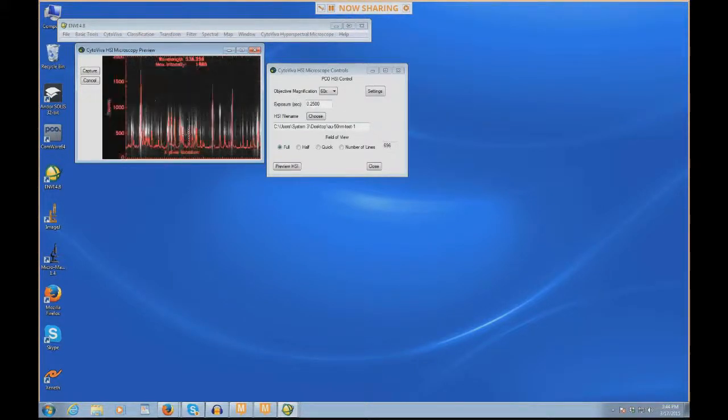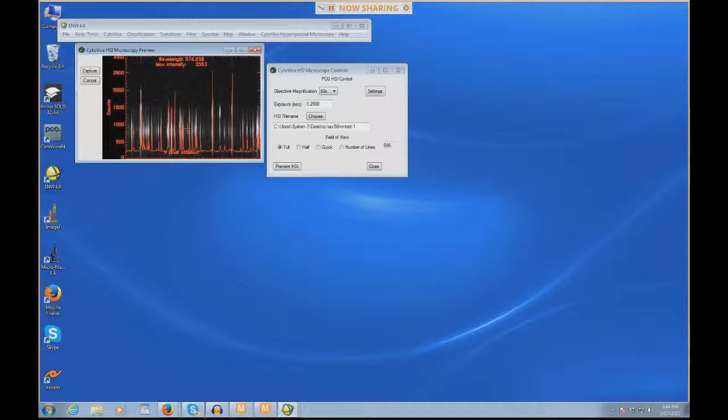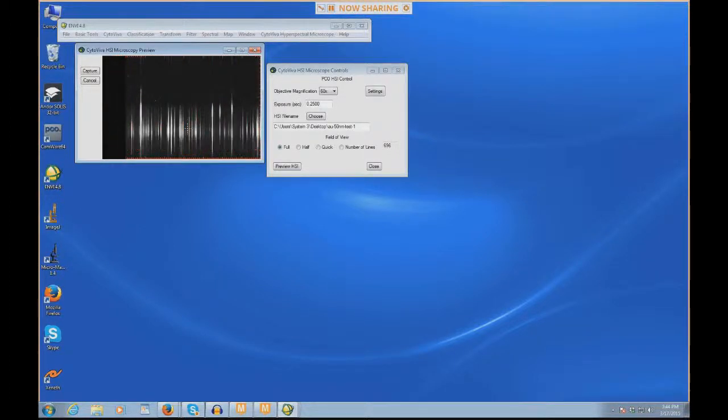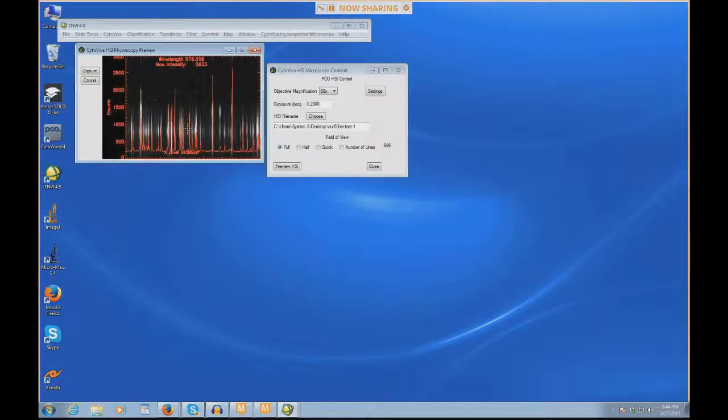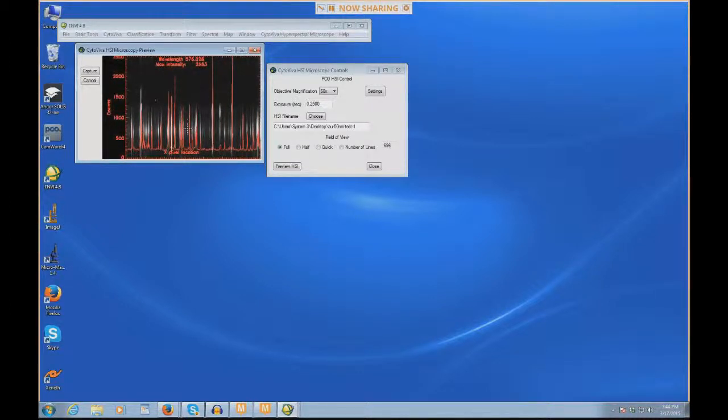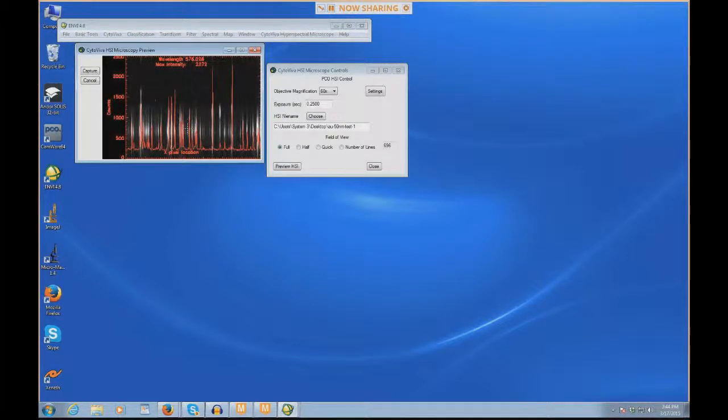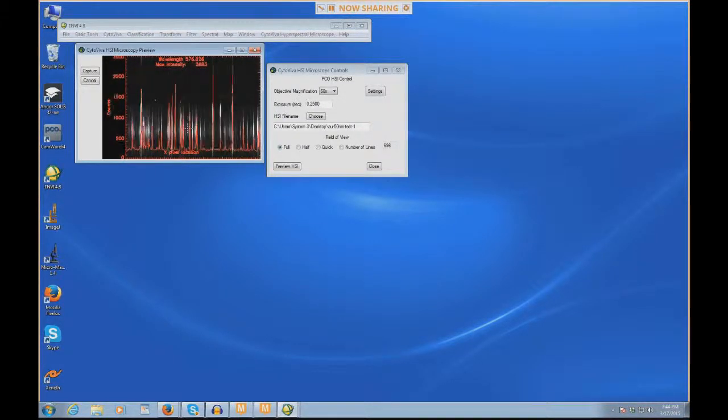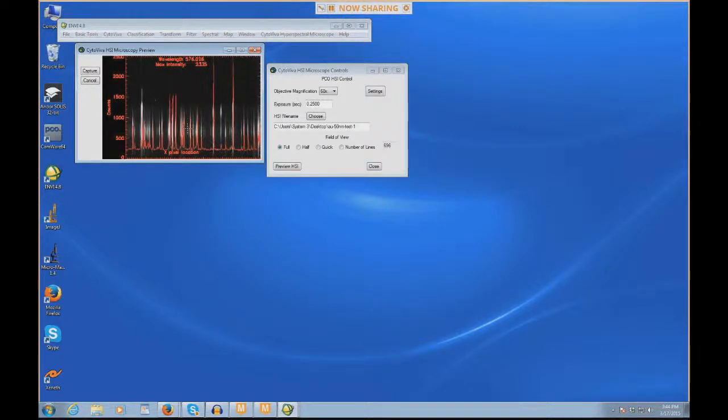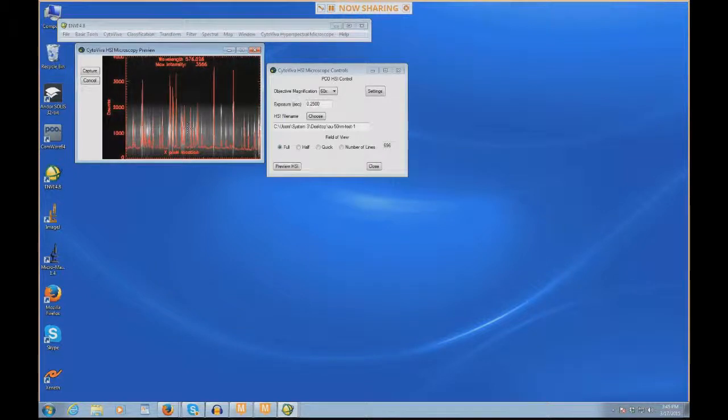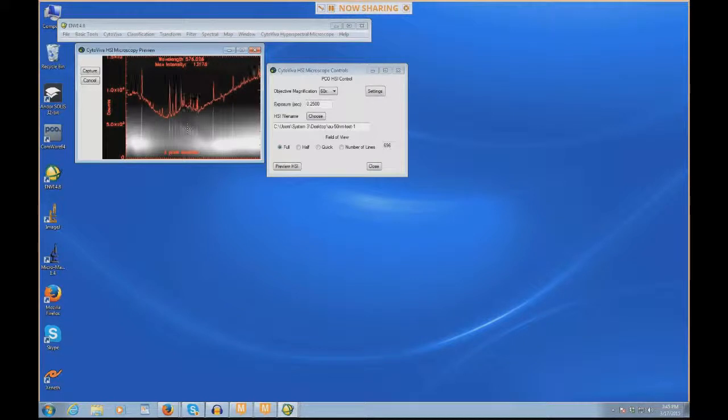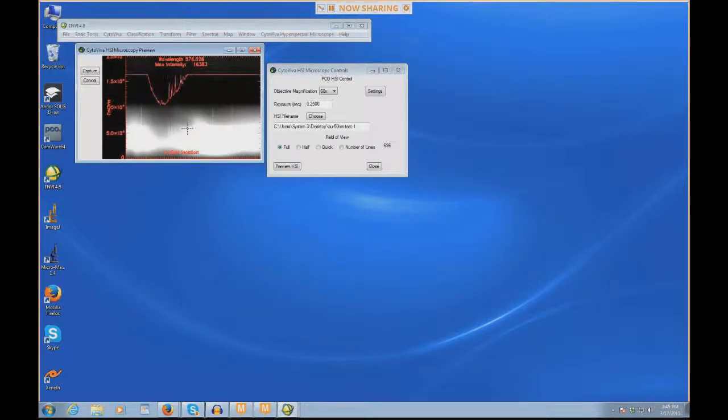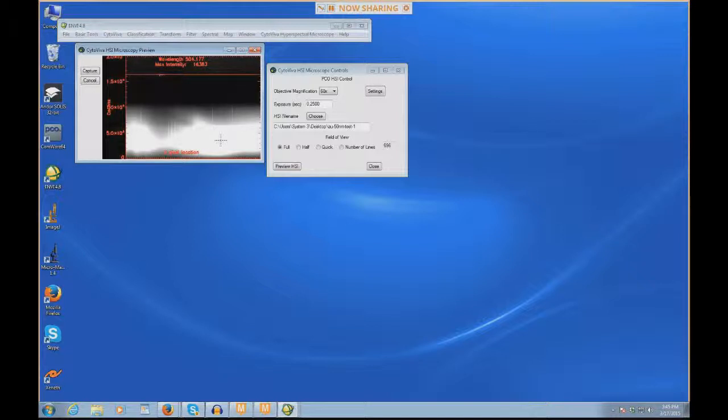Now I'm going to talk a second about these intensities. What is an acceptable intensity? With this camera, my general rule is that you want your intensities to be over 1,000. Anything below that could be considered too noisy. Obviously, going above the camera's dynamic range will make the camera clip, and I can show you what this looks like. I'm going to open up the iris on the objective. This is a 60x oil objective with a variable iris, which changes the numerical aperture. You see these flat lines here at the top. This is clipping. If I put the cursor over the very bright white light, we see max intensity is 16,383. This is the maximum dynamic range of the camera.